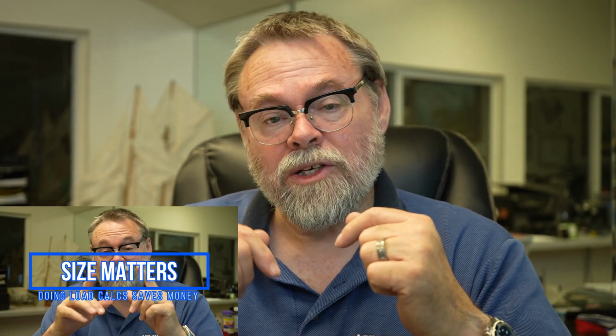So again, I can measure EER in the field, but I cannot measure SEER in the field. And now that we're SEER 2, it doesn't change. The calculations are still the same. It's just I measure the watts, and I measure the BTUs it's producing, and I divide it into it, and that gives me my EER, and then I can rate that piece of equipment. So I hope that explains SEER and EER for you.